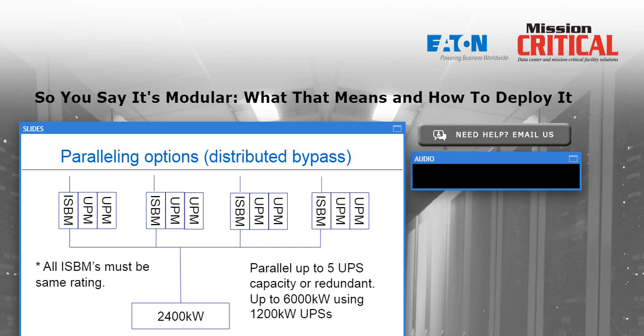So it becomes very handy to be able to offer a UPS system that is configurable and scalable. So a client may say, for right now, I only need 200 kilowatts, and for this other system, everything in the module, the enclosure is going to be the same, but I do need a little more power. I don't want to have to oversize the UPS because I don't have space in a typical mobile application. So a UPS system that can expand in minimum footprint gives a lot of flexibility for the manufacturer and the operator of a mobile system, while allowing the vendor of the UPS to offer the same product line with the same feature, benefits, controls, field service parts, etc., for an application that can vary significantly depending on what the end user wants to use.